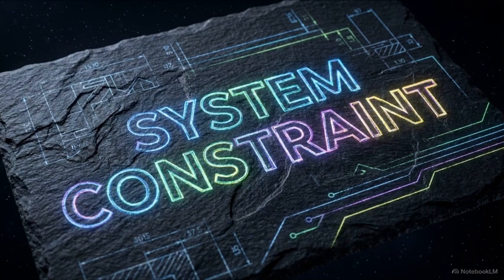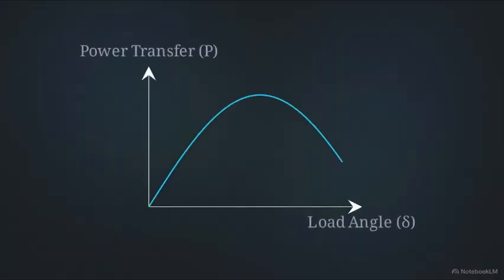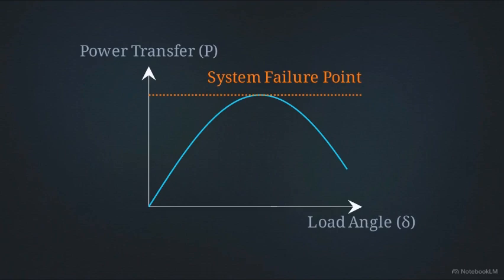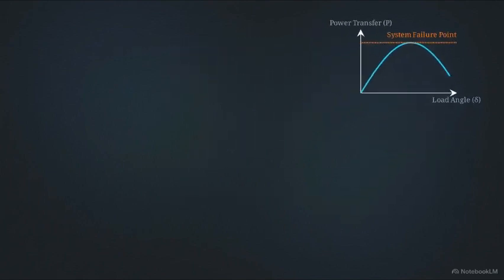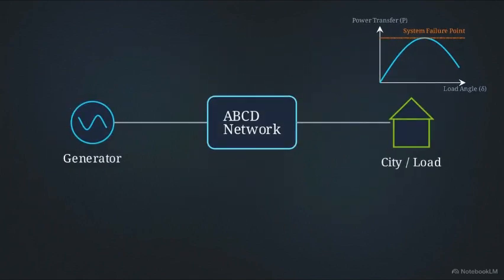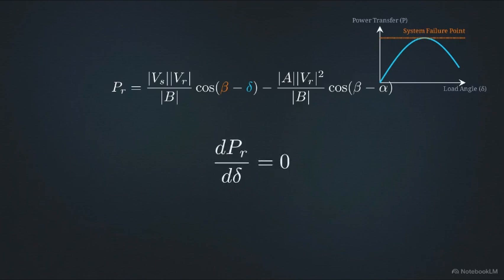Engineers define this constraint through the steady-state stability limit. It is the absolute mathematical boundary of how much power can be transferred over a line under marginally stable conditions before the system fails. This schematic outlines an ABCD network connecting a generator to a receiving city. The equation dictates the exact power transferred, calculated by balancing voltages against impedance and load angles. Finding the threshold of maximum capacity requires differentiating this equation. The maximum is reached strictly when the load angle exactly matches the impedance angle.